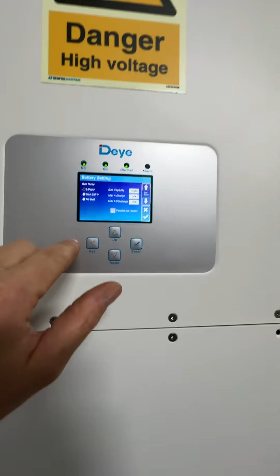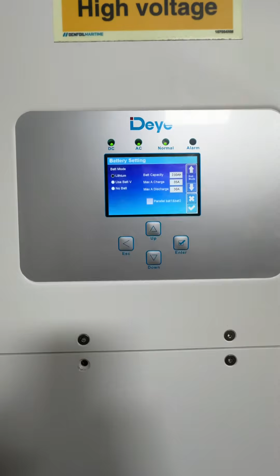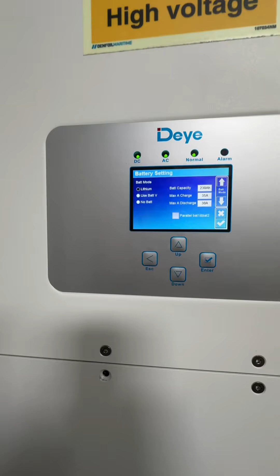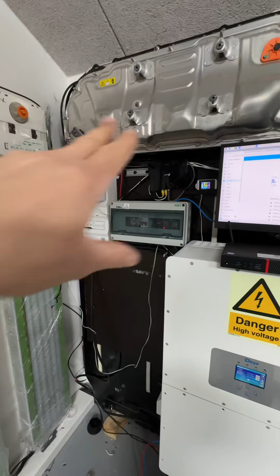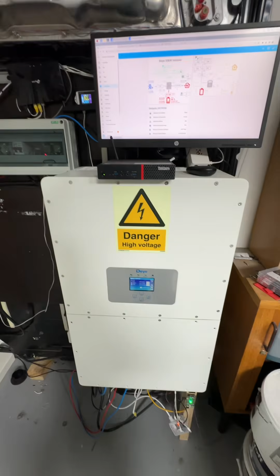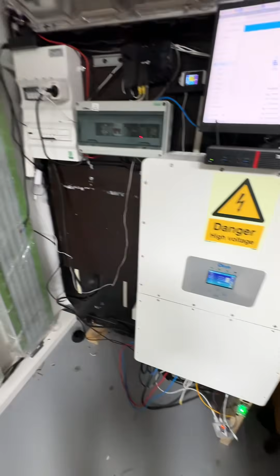Here you can choose what communication type to use: lithium, battery voltage, or no battery. In my case, I use lithium with CAN communication coming directly from the battery. If I put it in voltage mode, it will recognize both batteries since you have a double BMS, but in that case, when you have a higher battery and a lower battery, the higher one will discharge into the lower one.